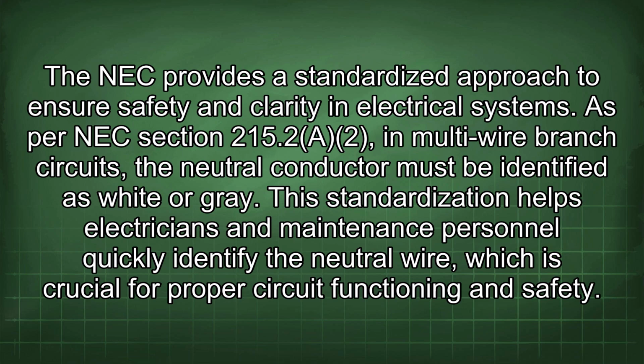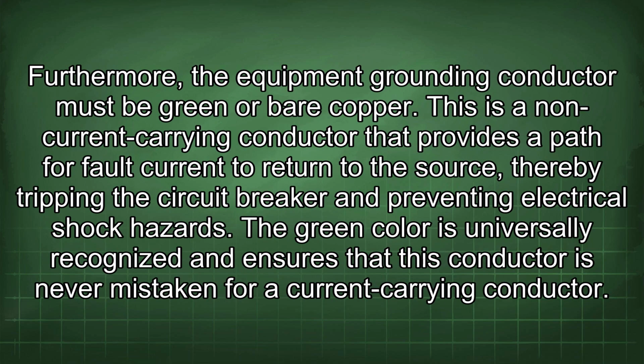This standardization helps electricians and maintenance personnel quickly identify the neutral wire, which is crucial for proper circuit functioning and safety. Furthermore, the equipment grounding conductor must be green or bare copper. This is a non-current carrying conductor that provides a path for fault current to return to the source, thereby tripping the circuit breaker and preventing electrical shock hazards. The green color is universally recognized and ensures that this conductor is never mistaken for a current carrying conductor.